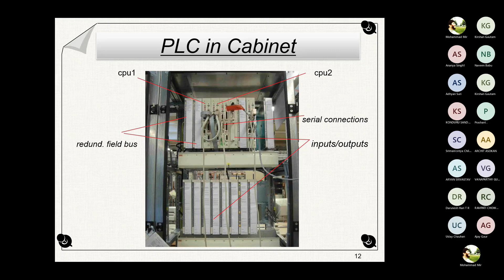Now, a very important thing in PLC programming is the PLC program scan - how the PLC basically works. This is called the scan cycle. One scan cycle consists of reading the input, then executing the program, then communicating with the output and updating it.